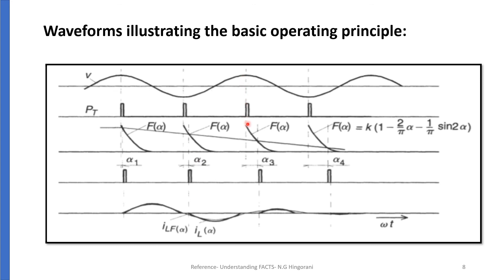In the third half cycle, the ILF characteristics and the required value of fundamental current are used. The point of intersection gives alpha 3. Starting from the peak of the voltage up to this point, a timer circuit is set and the pulse is triggered at that instant to obtain alpha 3 as the firing angle and hence achieve the required ILF value. By this method, ILF can be controlled in each half cycle to fulfill the reactive power requirement of the system using FCTCR.